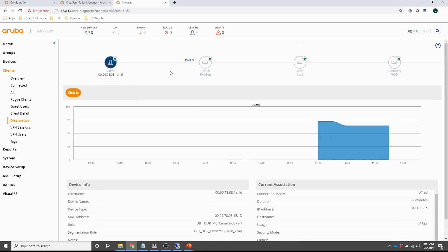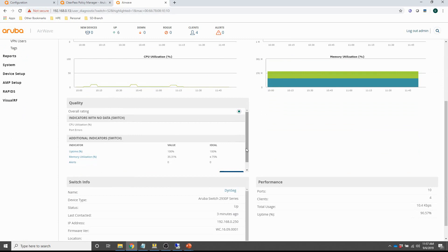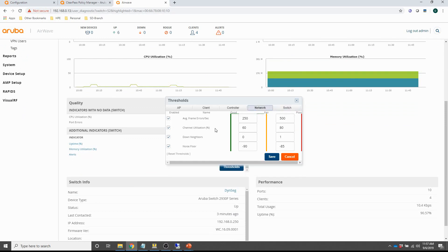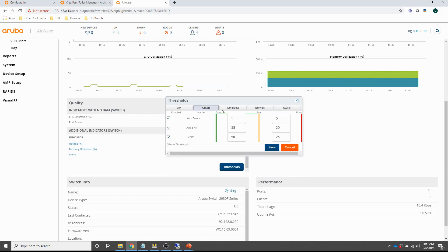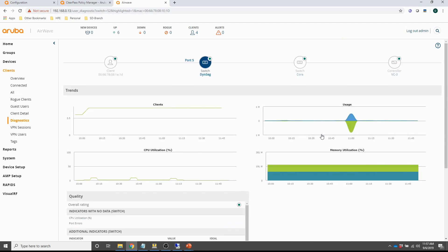You can also see these green dots on the device, which show that everything is fine. If a threshold were exceeded, this green indicator will change color — it will either turn yellow or red. For the thresholds, let me show you the switch. I can set thresholds for the relevant components — for the switch, for the network, for the controller — there are all kinds of thresholds, and if they are exceeded you'll get an alarm situation.